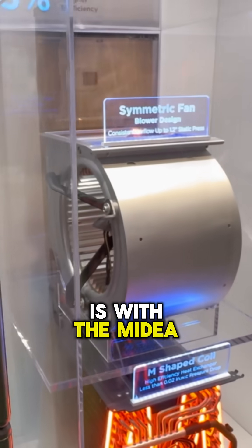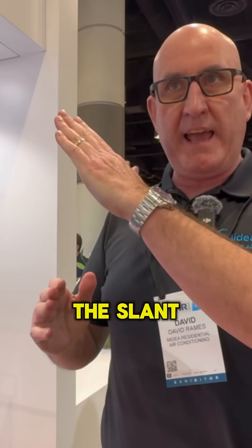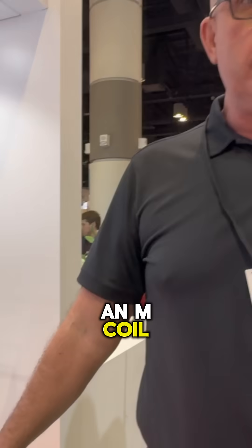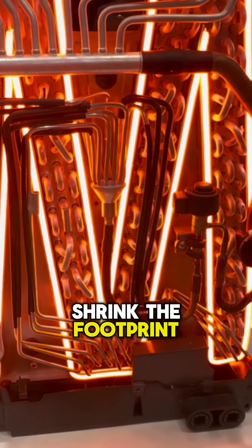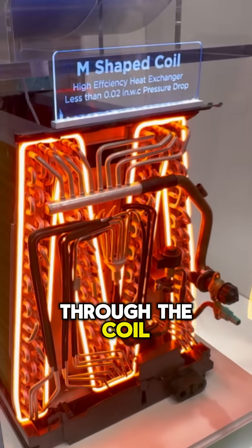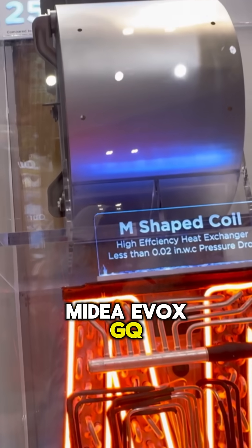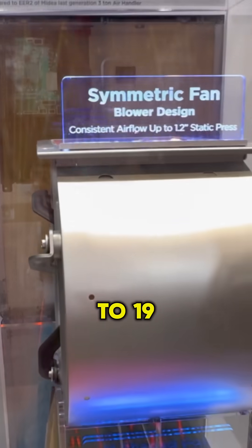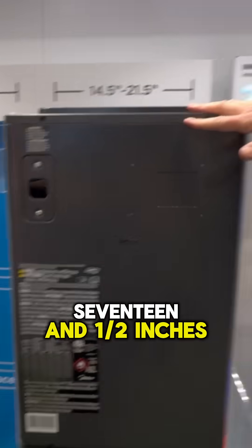So what we've done is, with the Midea EVOX GQ, we've gone from the conventional A-coil or the slant coil to an M-coil. Within that M-coil, what it allows us to do is shrink the footprint, so we can still get great airflow through the coil. One of the incredible things about this Midea EVOX GQ is we can get up to 19 SEER2 out of this product. Most high-efficient three-ton air handlers are 21 inches wide, but because of the M-coil, our three-ton is now 17 and a half inches wide.